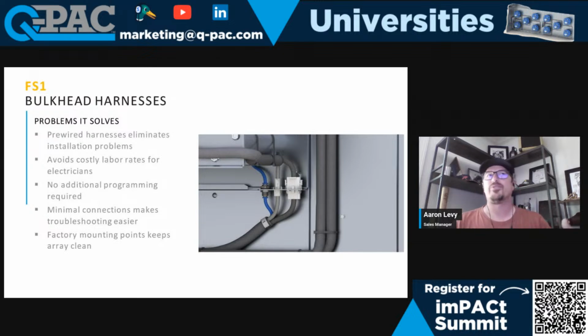All of our wiring harnesses solve the problem of having somebody come in and hand wire every solution. We provide the wiring harnesses from the quick connect box all the way to the fan, and all those connections are made by us. They're all plug and play with Molex plugs - they just snap together, very user friendly. It doesn't require any electrician side of it, there's no programming involved, and there's minimal connections to troubleshoot. You can easily figure out if there's a problem in a wiring harness, find it, and replace it. Once it's installed, you never have to remove those wiring harnesses, because all the wiring connections are made at the fan. Every replacement fan comes with that same connection whip you see in the picture, with the pressure tubing, the communication port, and the power port.